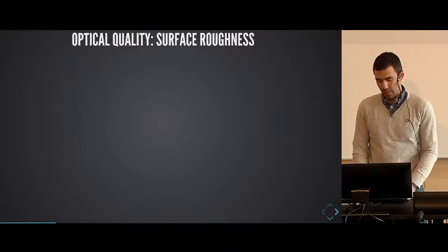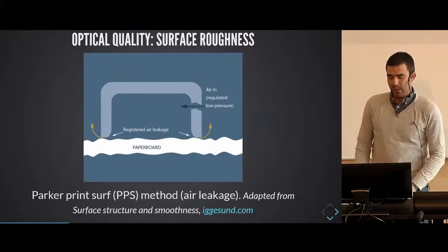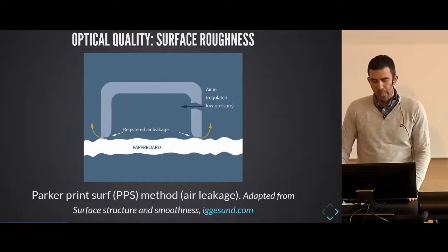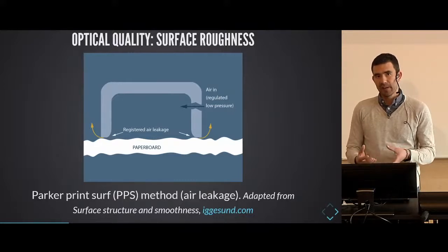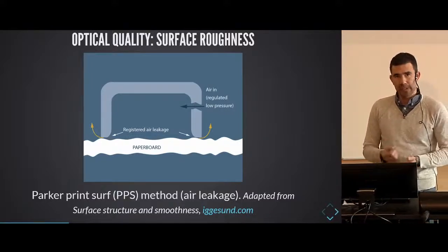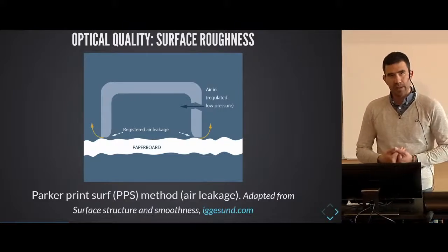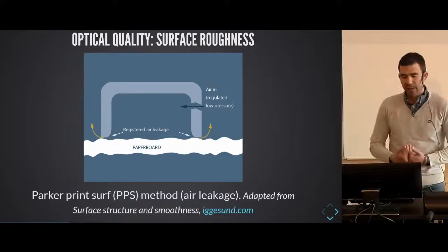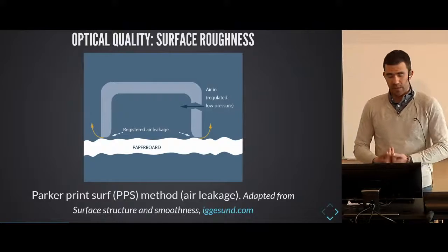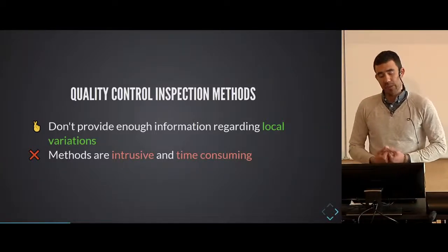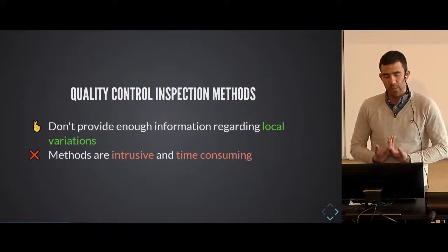Surface roughness is the number one parameter measured in industrial environments to assess the optical quality of high-quality products. Traditionally, paper manufacturers use air leakage methods — a device that relies on injecting air through a test device clamped to the surface of the material. It registers the air that leaks through the interface between the material and the device, and this air leakage is correlated to the surface roughness of the material. These quality control methods for inspection work well and basically do their task, but why do we need to improve them?